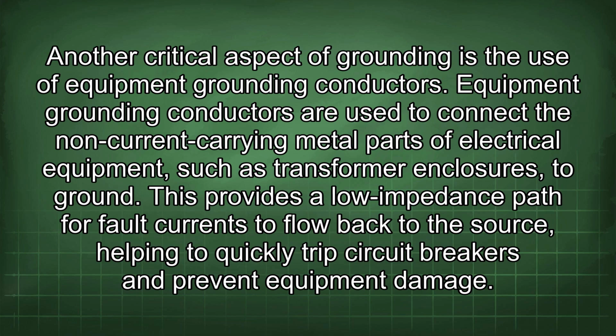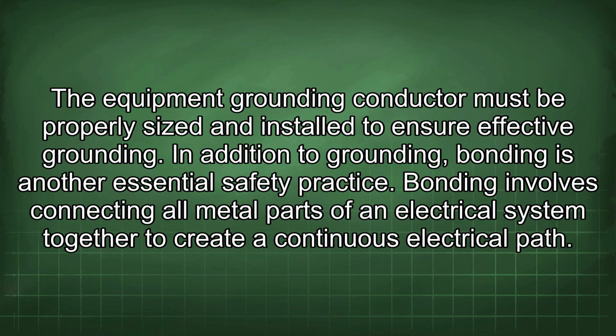Another critical aspect of grounding is the use of equipment grounding conductors. Equipment grounding conductors are used to connect the non-current carrying metal parts of electrical equipment, such as transformer enclosures, to ground. This provides a low impedance path for fault currents to flow back to the source, helping to quickly trip circuit breakers and prevent equipment damage. The equipment grounding conductor must be properly sized and installed to ensure effective grounding.